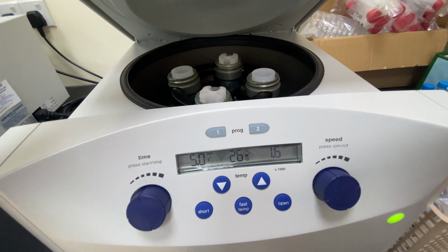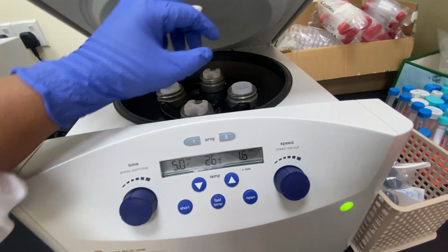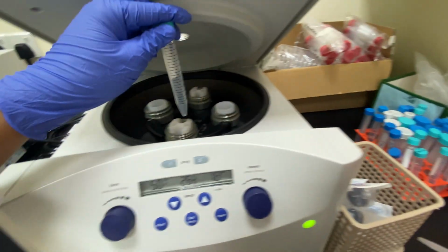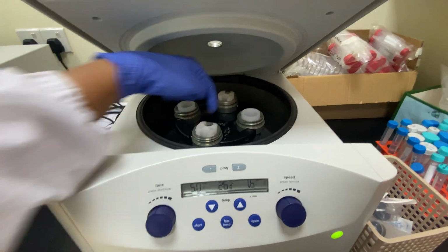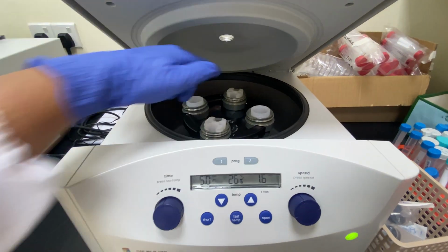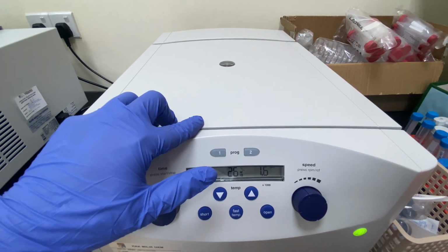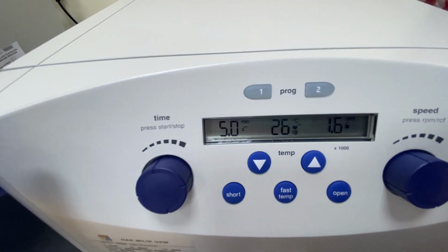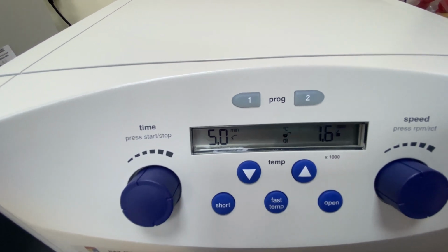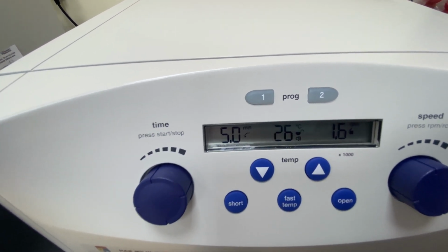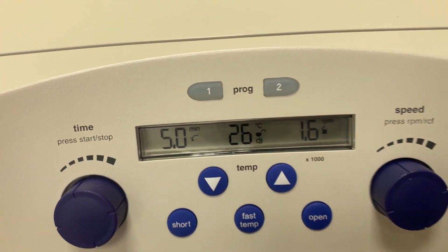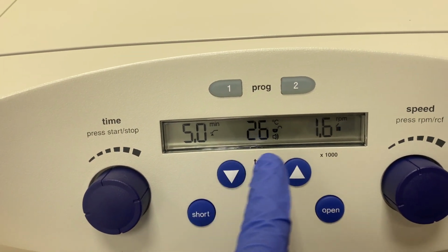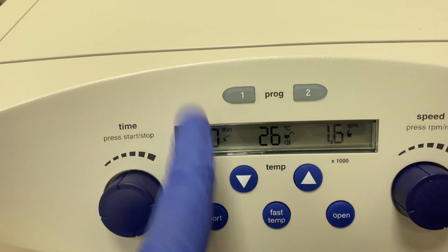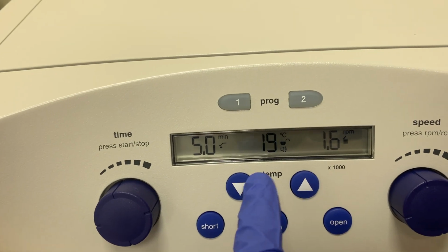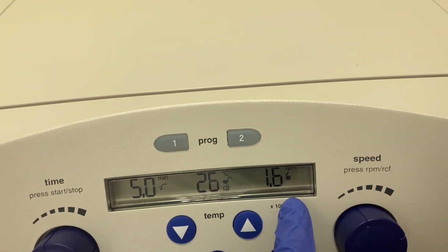So how do we set the speed? First, after you put your samples in here, remember to put the same weight on the opposite side to balance it. This has already been set to 5 minutes. The temperature follows the room temperature, and this one is the RPM.